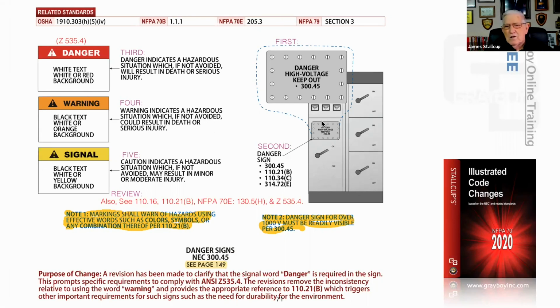Or look at it another way - say you had this equipment, and when you removed this cover you had to remove another cover, then you'd have a warning here. But the cover that gave you direct access to exposed, energized components and conductors would have your danger sign. Once you remove that cover, you're right in there with that stuff, so your danger sign would be there. You'd find that information over in Z535.